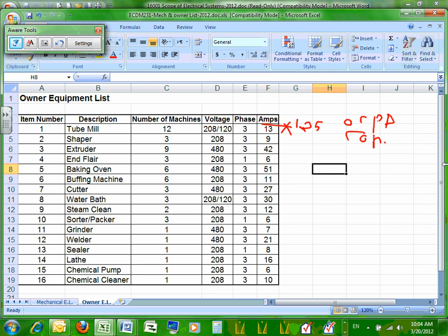Yeah. Maybe that contradicts what you've said, so I'm open to you fine-tuning this. But we're talking here about the SO ports that we're sizing to tie to the equipment, not the service. With the service, the demand and the continuous will cancel each other. Yeah, that's true. So what I've said is you could apply the demand as we collect those loads back at the next level and going further up. But I want that branch circuit, just as Chad has said, at 125% minimally times that continuous load. So we'll do the SO ports that you tie to the bus ducts. Okay.